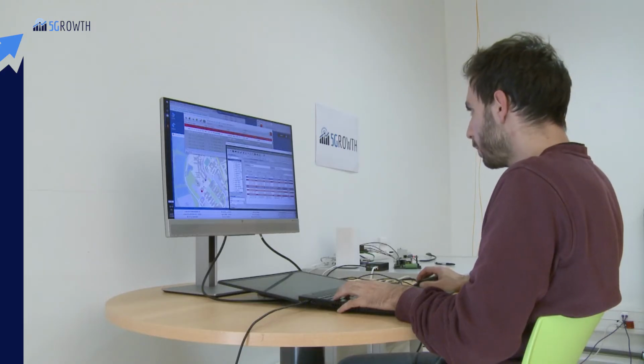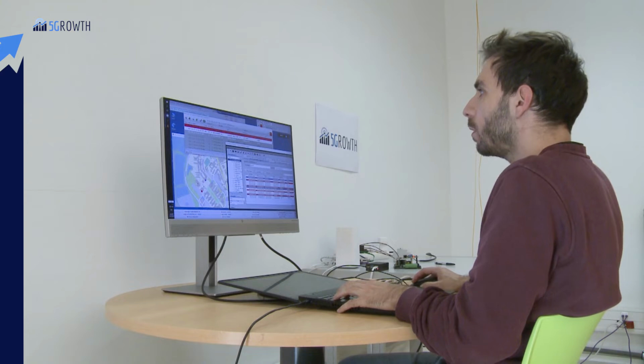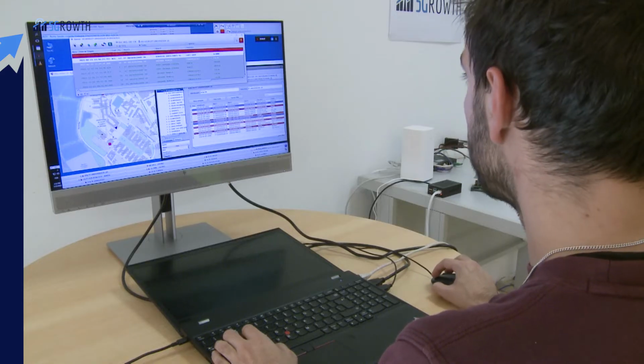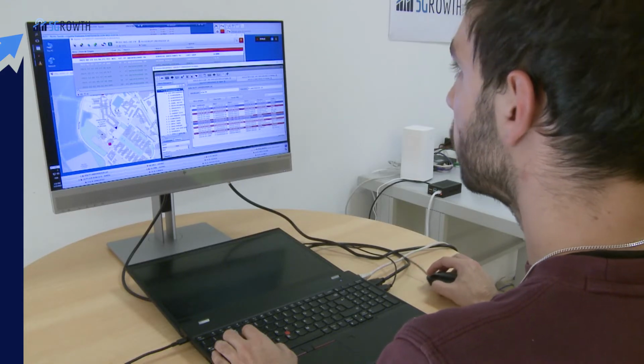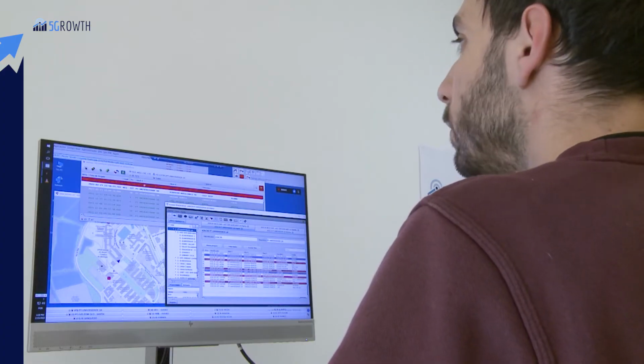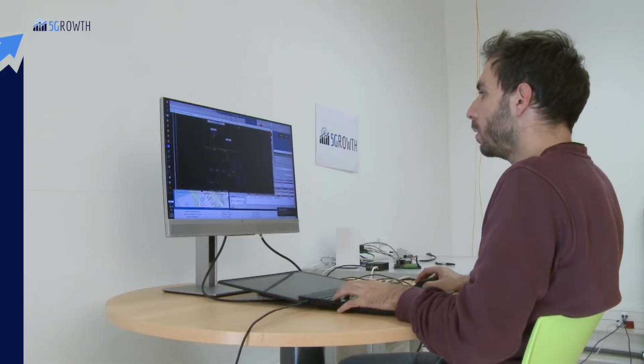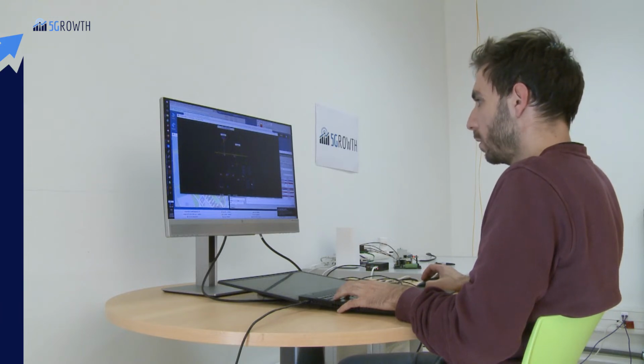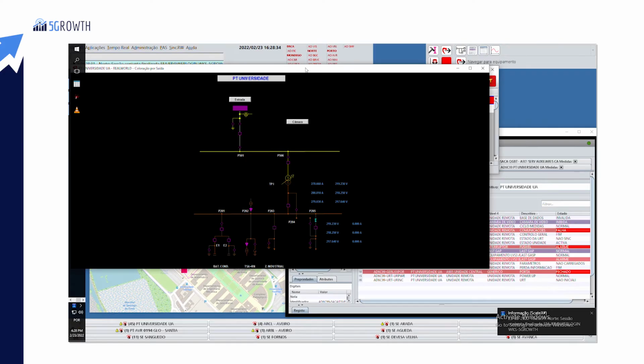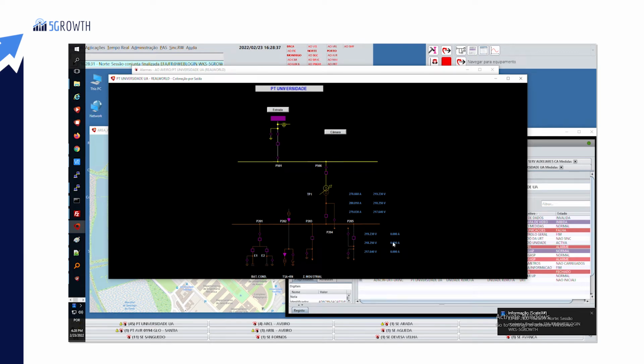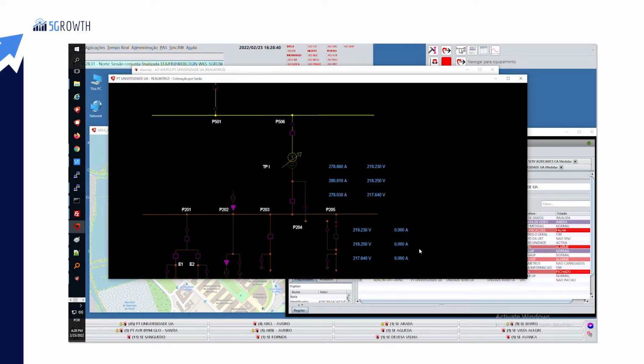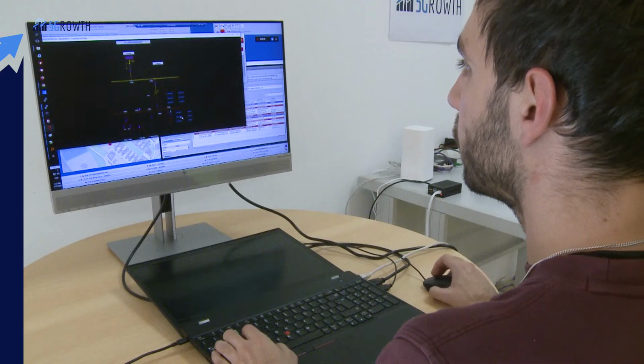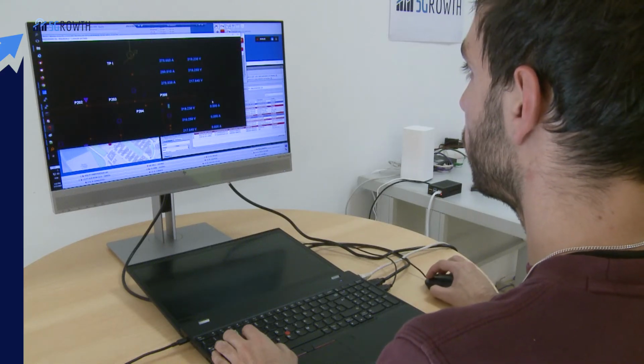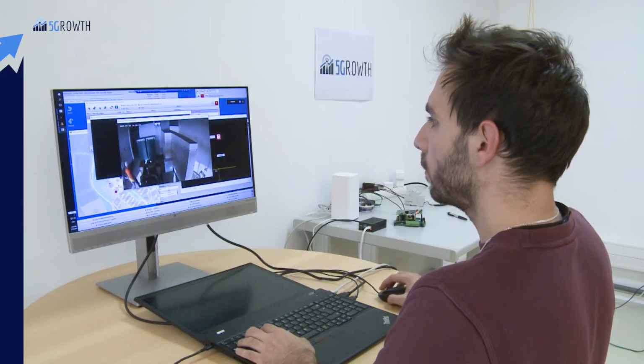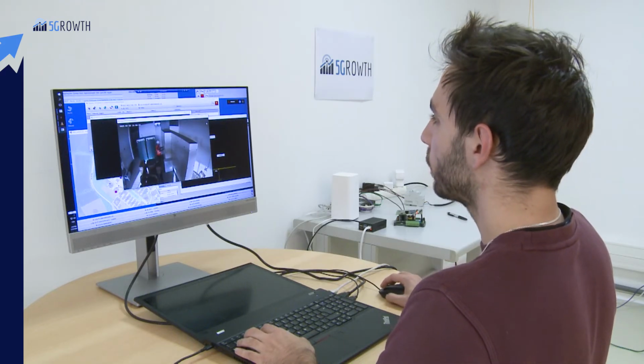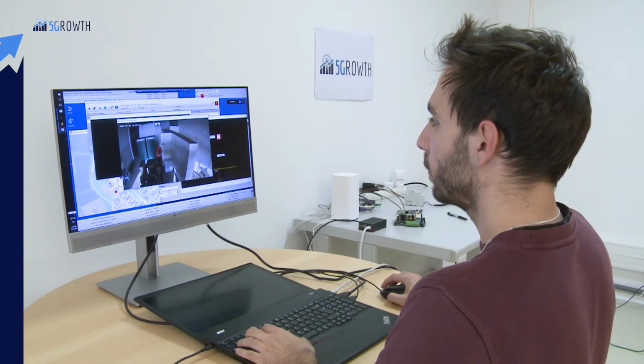To ensure a reliable real-time operation of the network and a smooth experience for the operator, a sustained low latency on the communications network is mandatory, not exceeding 100 milliseconds. The operator will then track down the abnormal event just arrived, opening the single-line diagram of the problematic substation from the alarm list entry. The diagram exhibits a set of real-time live information concerning the secondary substation telemetry, measurements like current and voltage, and signals like a blown fuse or an actuated intrusion detector. The operator may open a video streaming transmitting from inside the substation to get further information about the root cause of the abnormal event.